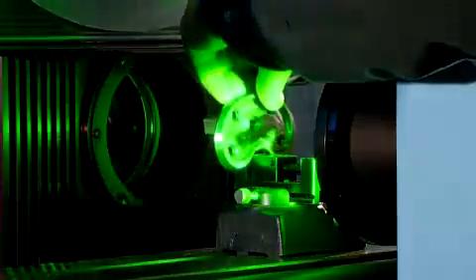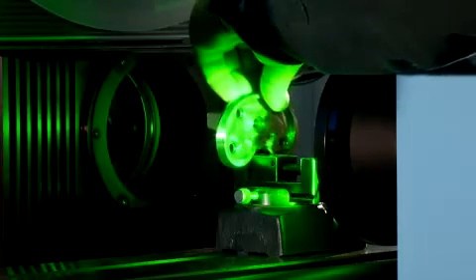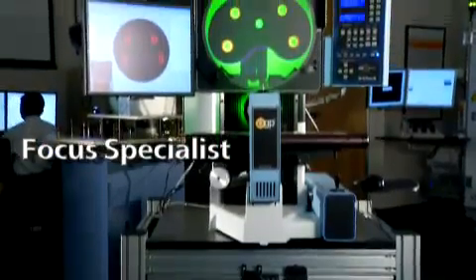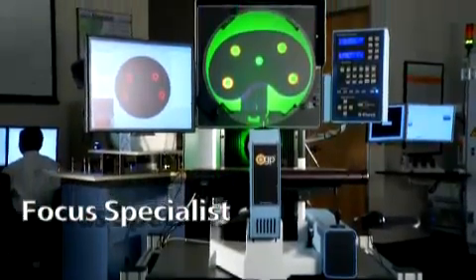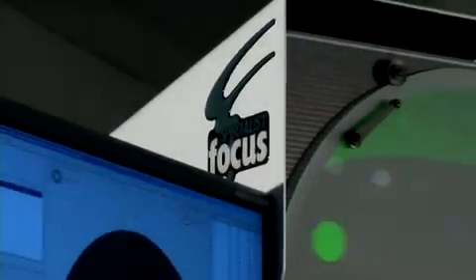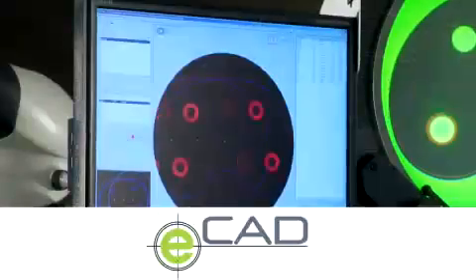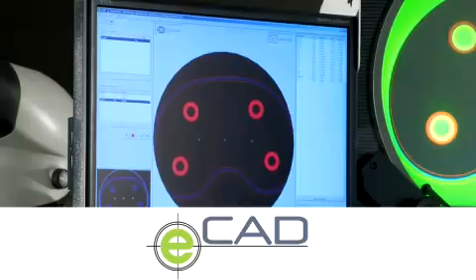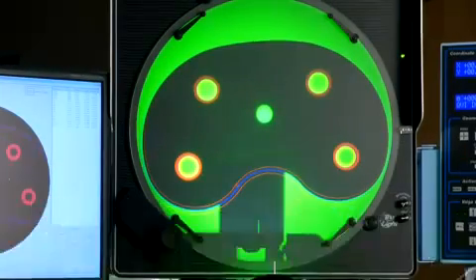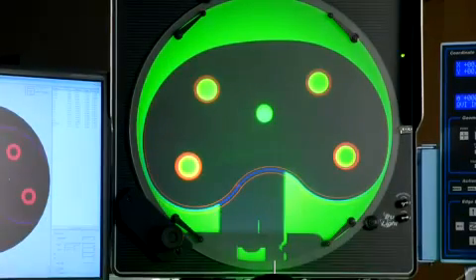This part could have 2D requirements only, in which case the type of machine best suited may be a comparator. OGP has transitioned comparators into 2010 technologies with features such as ECAD, an electronic overlay software that projects CAD file nominal and tolerance zones onto the comparator screen.